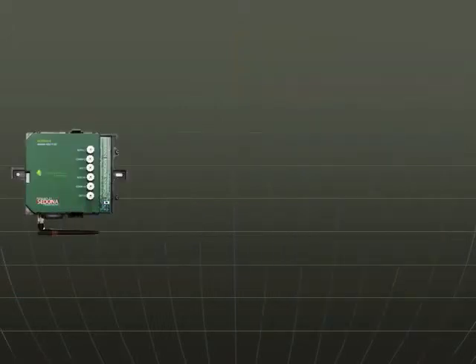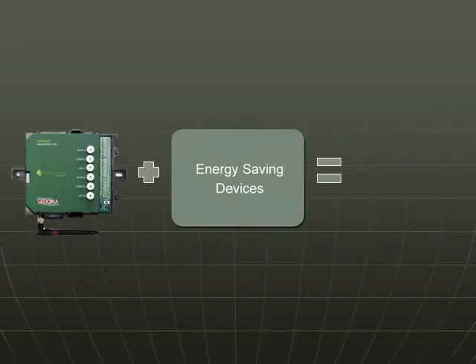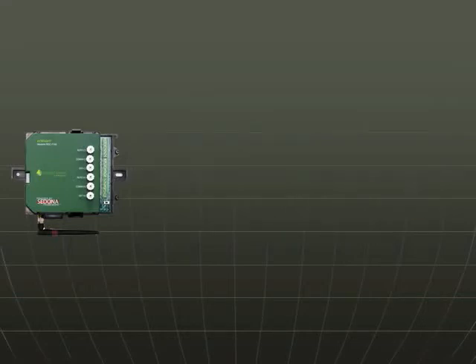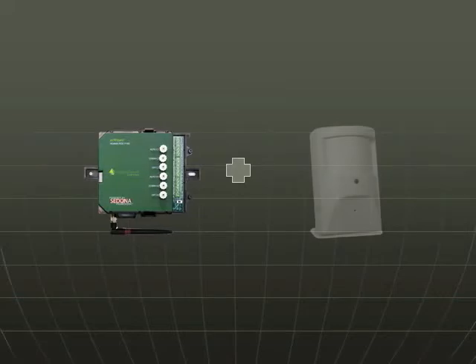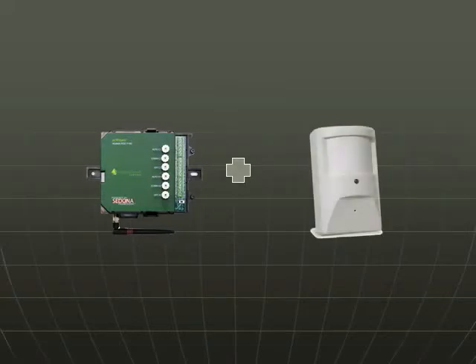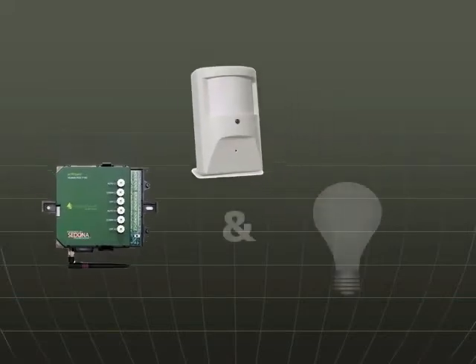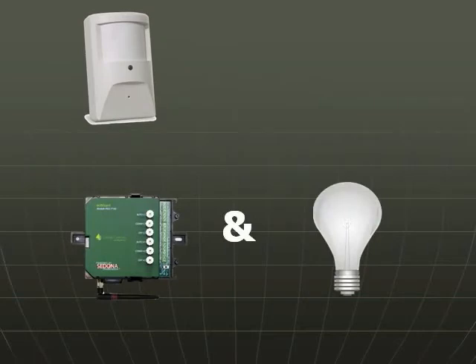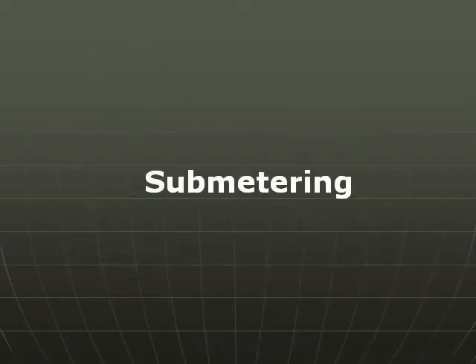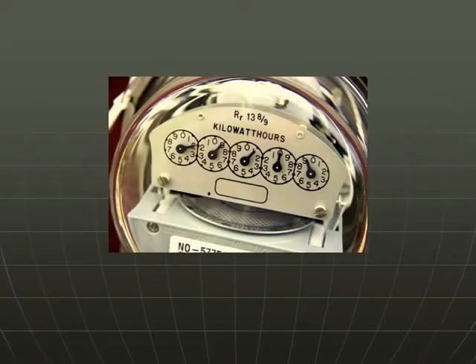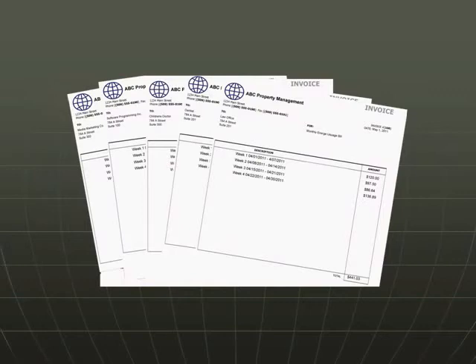The ecWizard DDC control system enhances the savings and payback for other energy-saving devices. When used with motion detectors, zone set points can be raised and lowered to accommodate vacancies when in occupied mode. It makes motion detectors more energy efficient because now it can turn off the lights and HVAC. When used with wireless sub-metering, the ecWizard can provide calculated HVAC costs. This capability provides for total accountability of energy usage of the tenants or occupants.